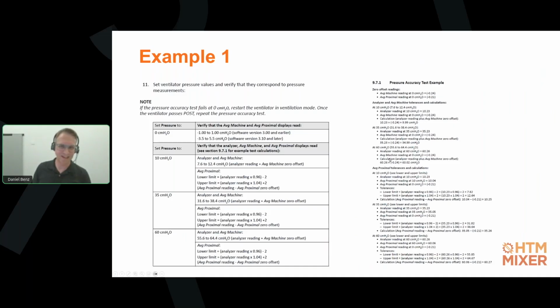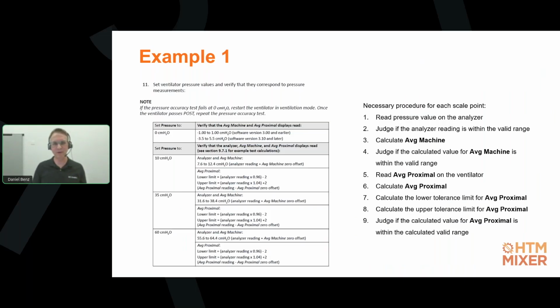And as you can see, it's not that easy. So we detailed it a little bit for you. Per scale point, they want you to go through 9 steps of reading values, calculating values, and then finally judge if the calculated values are within the calculated ranges. Of course, it's important to be trained on the procedures of the ventilators you are testing, but procedures like the one we have just discussed as an example can be very cumbersome and prone to errors.